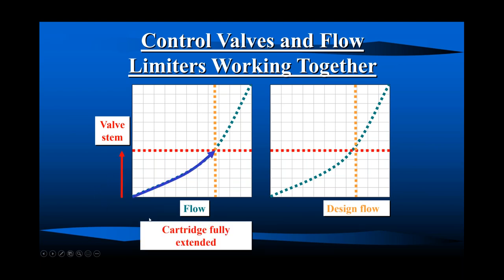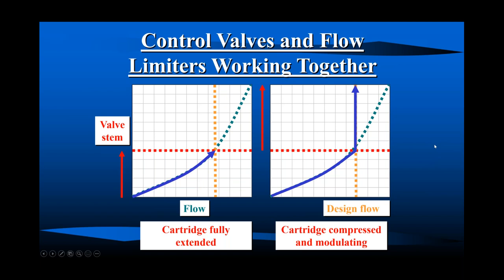Valve stem is opening. The cartridge is fully extended. It's not doing anything. It's a fixed orifice. The valve, again, has full authority. But the dynamics of the system, the pressures are all over the place. So differential pressure across that control valve tries to put a whole bunch more flow through that control valve than it actually needs. So before that control valve modulates back down, that pressure tries to overflow that coil. And that's where our flow limiter comes in. That's when the cartridge starts modulating, providing a variable orifice and limiting the flow. So no, they do not fight each other. They work rather well together.